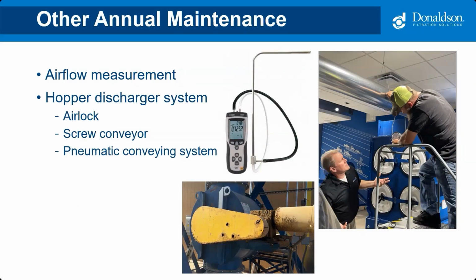Last couple of things that are a bit more technical that we like to recommend. I don't have time to get into the specifics of how you do it, but Donaldson can help you. We do recommend that you do an airflow check once a year, just to make sure your dust collector is still running at design flow. There's a handheld flow meter that you probe the duct with, and there's a very specific technique to doing it, so the person needs to be trained on that. And it's a good overall check that says, hey, is my collector still flowing the way it's supposed to when it was designed? And if it's not, that's where you can ask other questions.